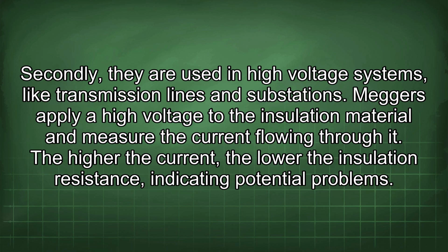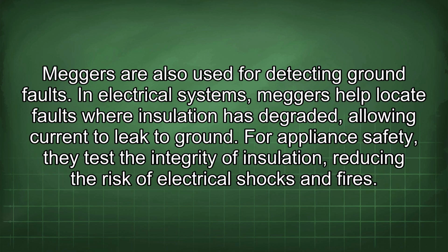Meggers apply a high voltage to the insulation material and measure the current flowing through it. The higher the current, the lower the insulation resistance, indicating potential problems. Meggers are also used for detecting ground faults. In electrical systems, meggers help locate faults where insulation has degraded, allowing current to leak to ground. For appliance safety, they test the integrity of insulation, reducing the risk of electrical shocks and fires.